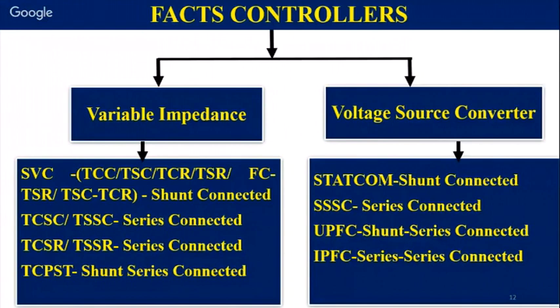Then the series connected ones are thyristor controlled series capacitors, thyristor switched series capacitors, thyristor switched series reactors, and phase shifting transformers. In voltage source converter type FACTS, there are no conventional equipments used like inductance and capacitor banks. The effect of leading or lagging current is produced by the semiconductor devices, such that their phase shift will be as if the current is leading the voltage, that is capacitive, or lagging effect.